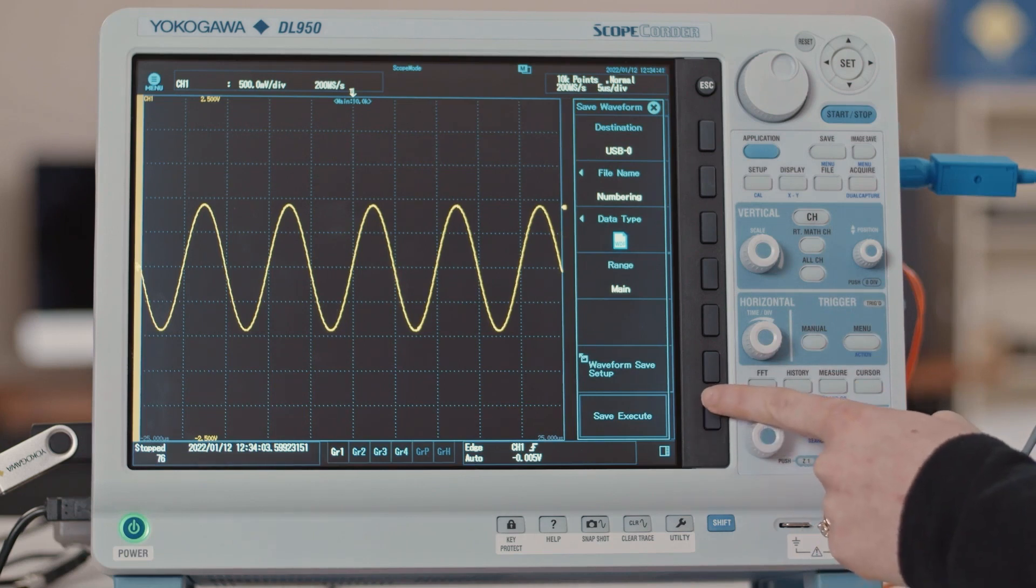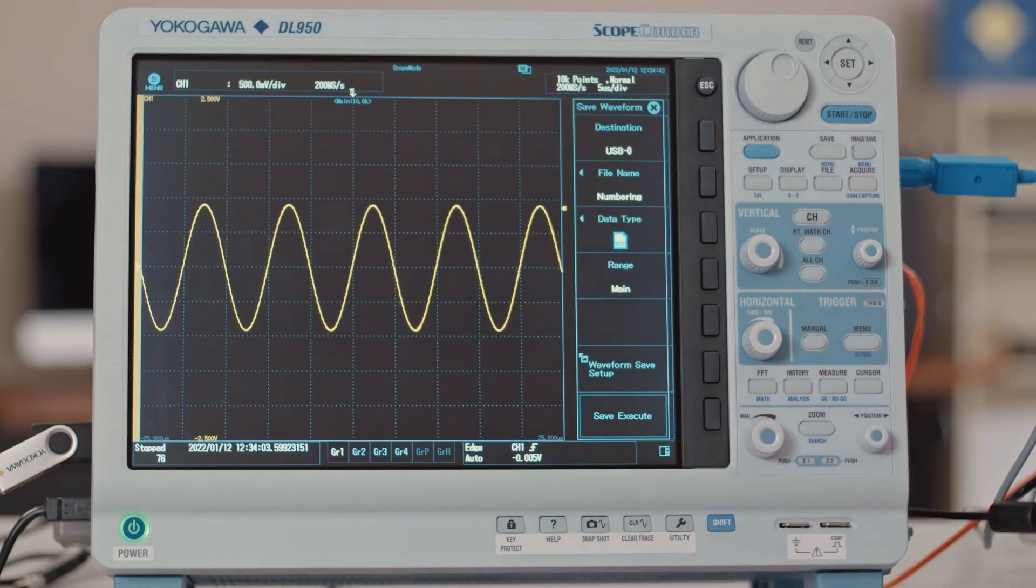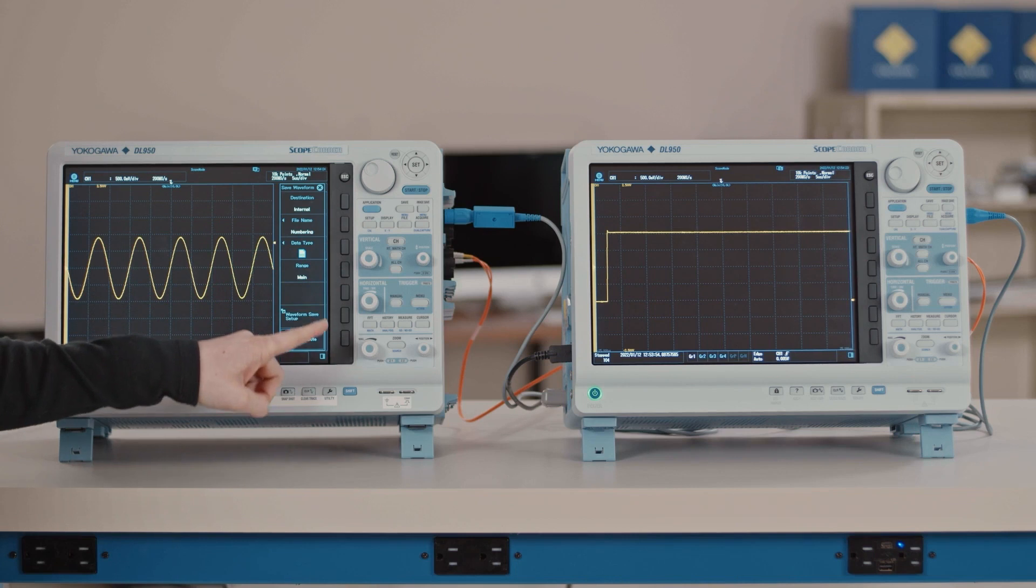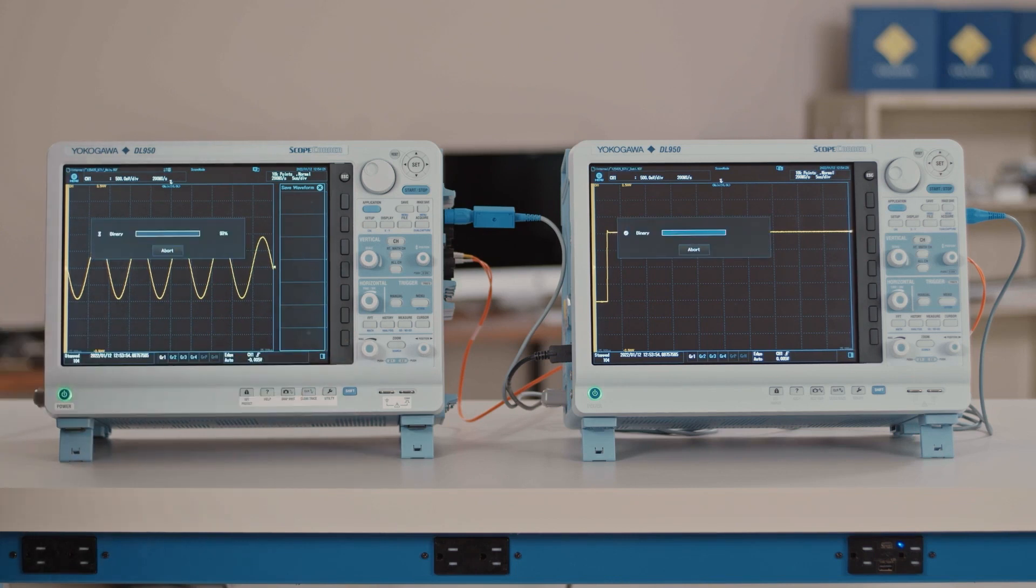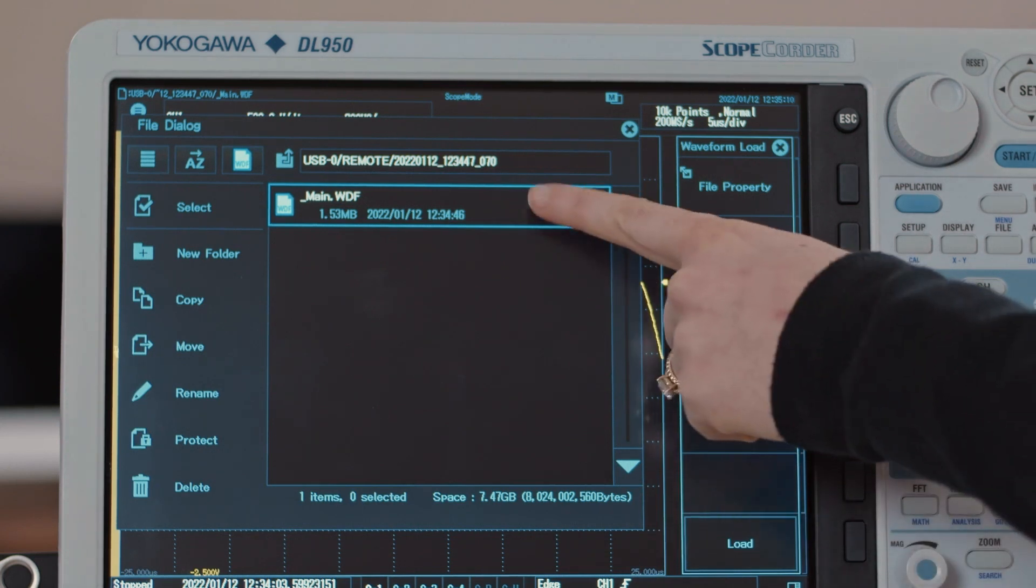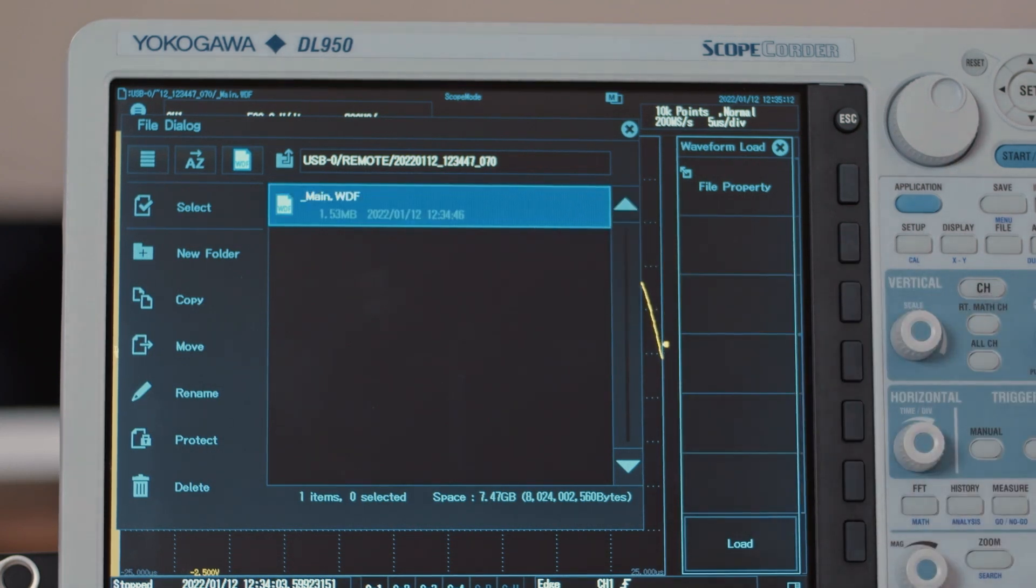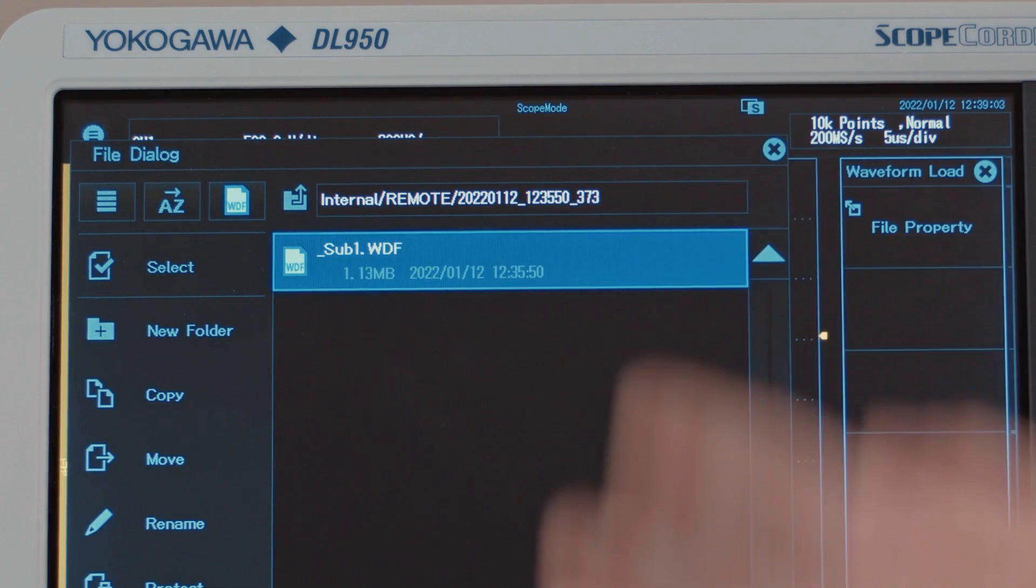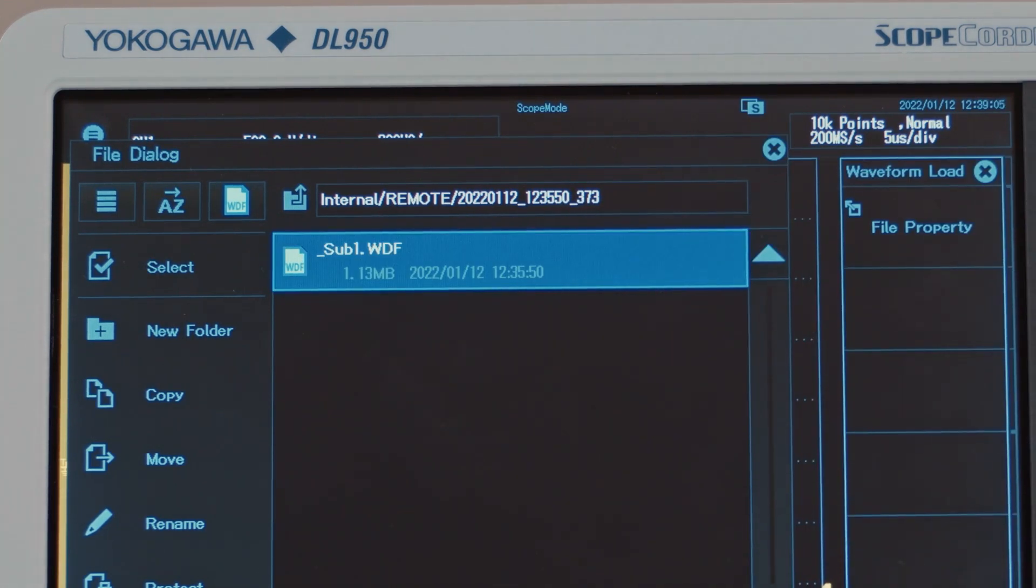The save settings need to be set on each DL950, but when you press Save Execute on the main unit, the subunits will simultaneously save their waveform data. Files are saved in folders automatically named by date and time. The main unit files are saved with an underscore main at the end and subunits are saved with an underscore sub and the number corresponding to which subunit it is.